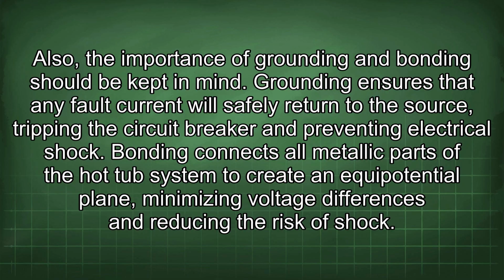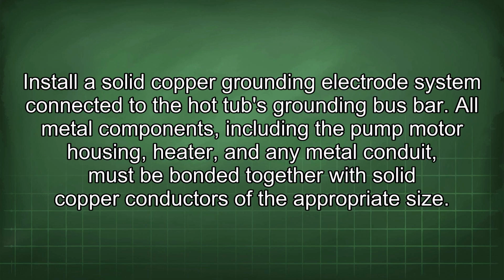Bonding connects all metallic parts of the hot tub system to create an equipotential plane, minimizing voltage differences and reducing the risk of shock. Install a solid copper grounding electrode system connected to the hot tub's grounding bus bar. All metal components, including the pump motor housing, heater, and any metal conduit, must be bonded together with solid copper conductors of the appropriate size.